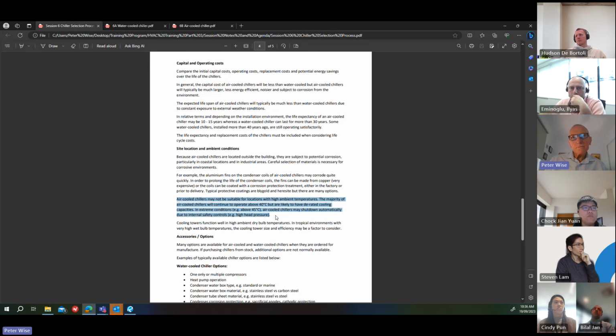And if you've got an ambient temperature that occurs occasionally, or even quite often at 45 degrees, you need to look at that, because you're going to lose capacity with an air-cooled chiller. Also, they may shut down automatically under their own safety controls. So if the head pressure is going up because of the high ambient temperature, they might just turn off. They won't come back on again until the head pressure drops, and you'll go through the cycle of starting and stopping. So that's a factor to consider.